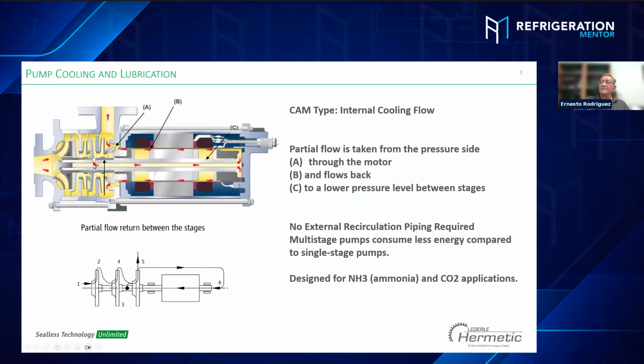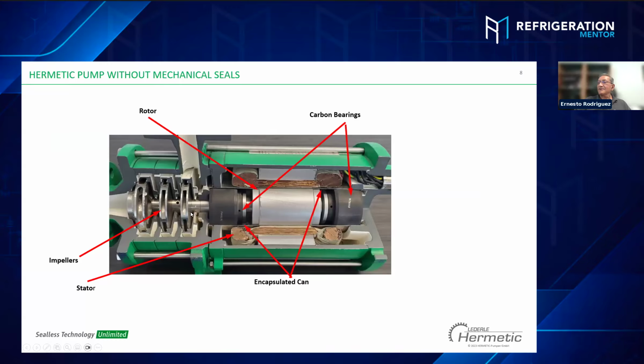to the shaft, and we have a little orifice right here, and this orifice is going to make the lubrication of the pump. We can see in this cutaway the orifice right here. This orifice means you have the discharge of the pump. We have high pressure right here, and it goes direct to the bearings, goes to lubricate the pump, and goes back inside the shaft. And this is the way the refrigerant returns and starts the process of circulation. It's a very simple design. It's not complicated. To disassemble the pump is very simple. You can see it's only a few parts.